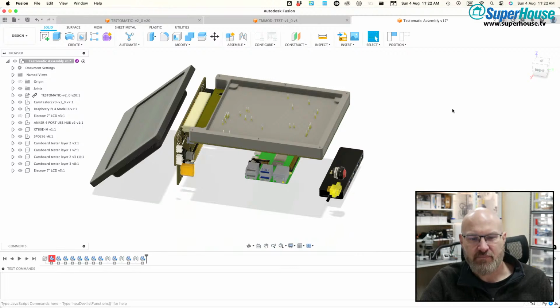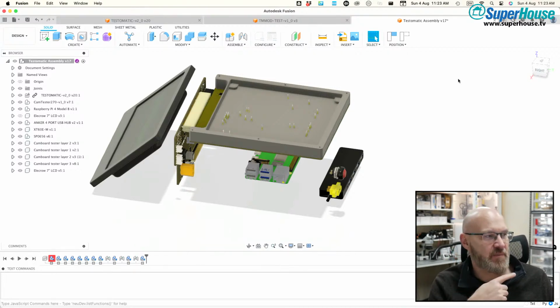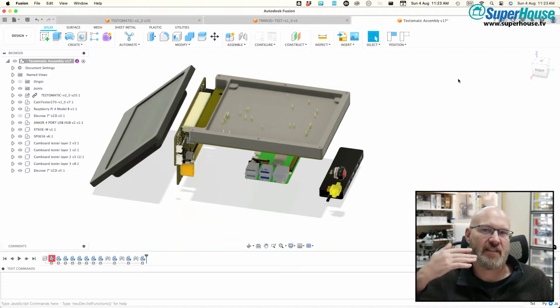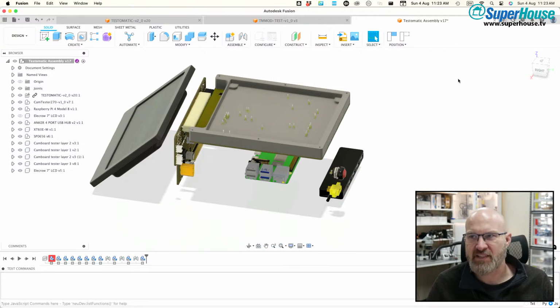Outside the box asked, how much does wear affect its operation? Could there be substantial difference between your test unit and a field unit? Ah, that is an excellent point. So Crispian said, how much does wear affect its operation? Could there be substantial difference between your test unit and a field unit? And in a similar vein, does using that same unit for testing over a period of time mean that its behavior has changed? For example, wear in the bearings meaning the tests I'm doing now are different to the tests I was doing a year ago. Test reproducibility, that is a very good point.